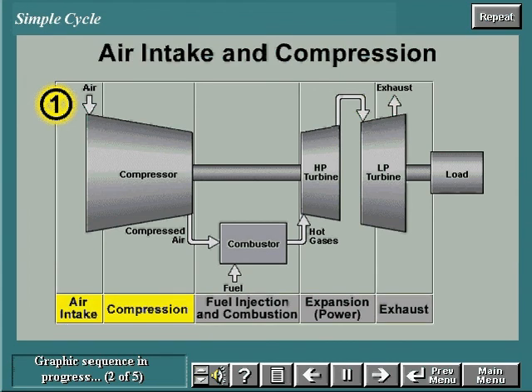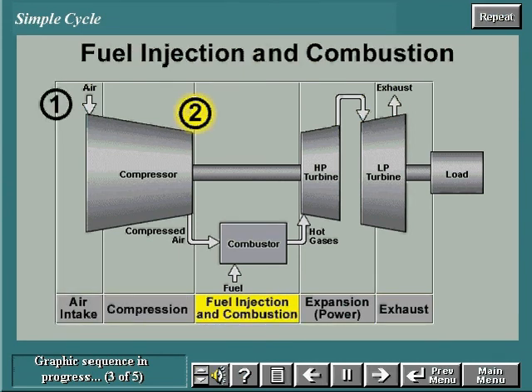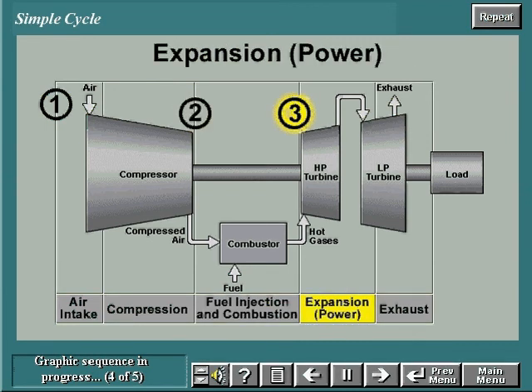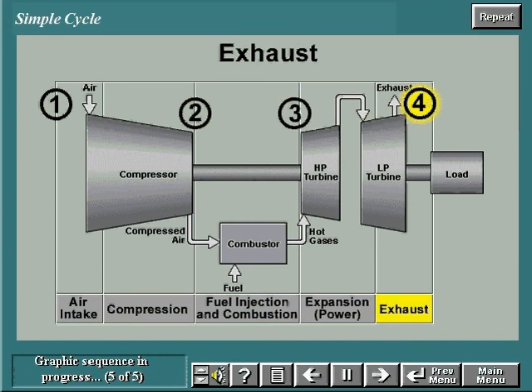At point one in this diagram of the simple gas turbine cycle, air enters the compressor and is compressed to a higher pressure. The high-pressure compressor discharge air at point two is mixed with fuel in the combustor. The combustion gases at point three enter the turbine where they expand and cool, performing work on the rotating turbine shaft. The combustion gases are then expanded to atmospheric pressure and exhausted to the atmosphere at point four.